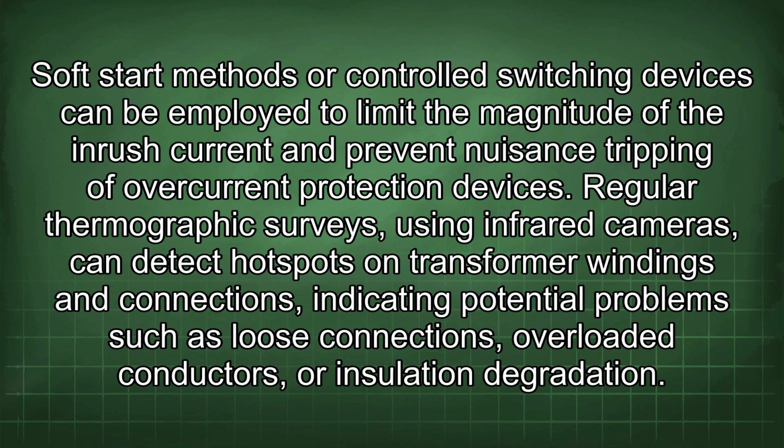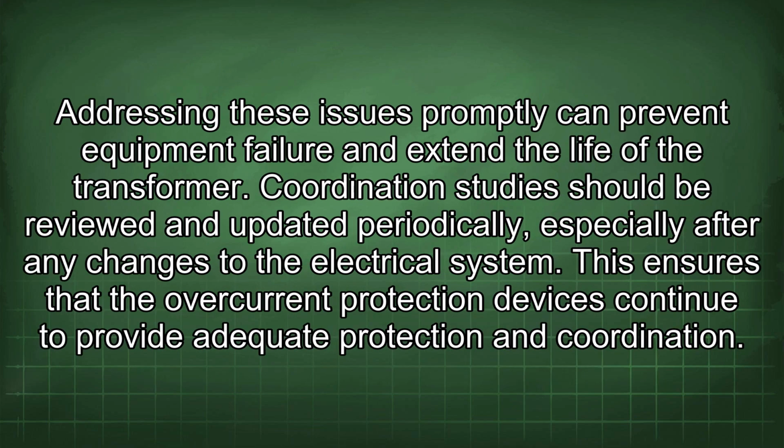Regular thermographic surveys using infrared cameras can detect hotspots on transformer windings and connections, indicating potential problems such as loose connections, overloaded conductors, or insulation degradation. Addressing these issues promptly can prevent equipment failure and extend the life of the transformer.